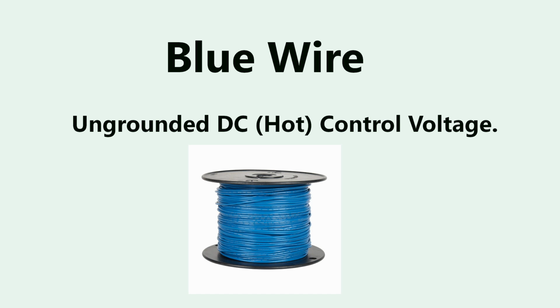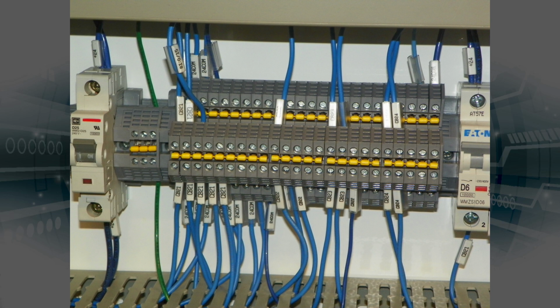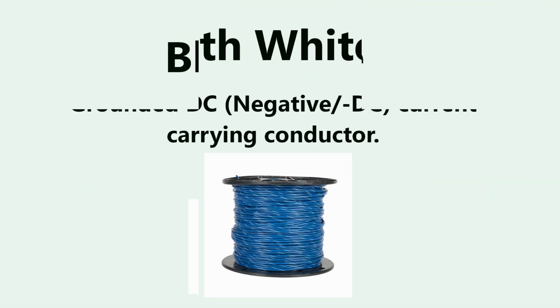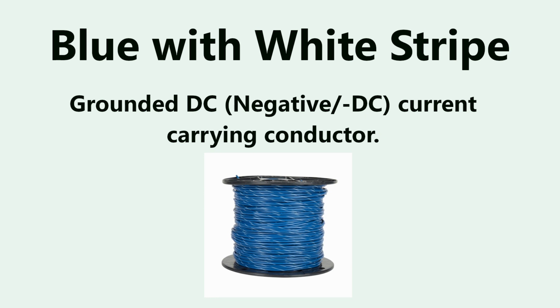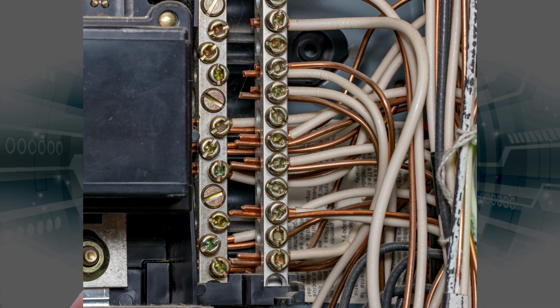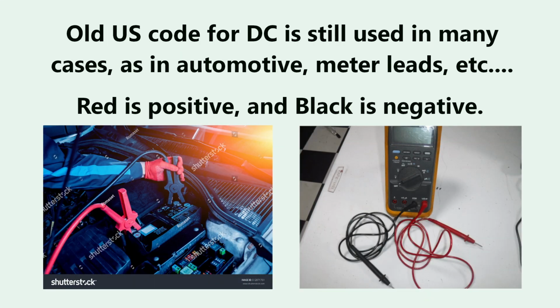You've also got blue wire, which signifies ungrounded DC control voltage, or plus. The plus voltage is blue. And then you've got blue wire with a white stripe, and that signifies the common DC voltage, which is commonly known as the negative. Neutral can be white if you're using US code, or it can be gray if you're using European code. Typically, the old DC designation for the US is red is hot and black is common. You can see this on things like cars, and even the meter leads for a meter are going to be red and black, and the red is typically hot and the black is typically common.